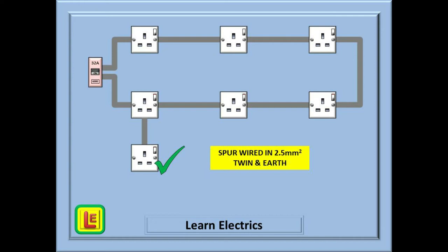This is a good situation. Yes, it is 27 amp cable and yes, it is a 32 amp breaker, but as it is a 13 amp socket outlet we should not expect to draw the full 27 amps. The plug top fuse should have blown long before then.